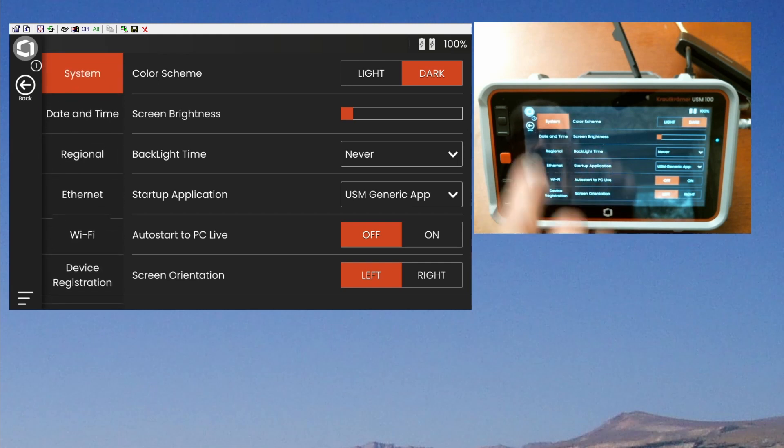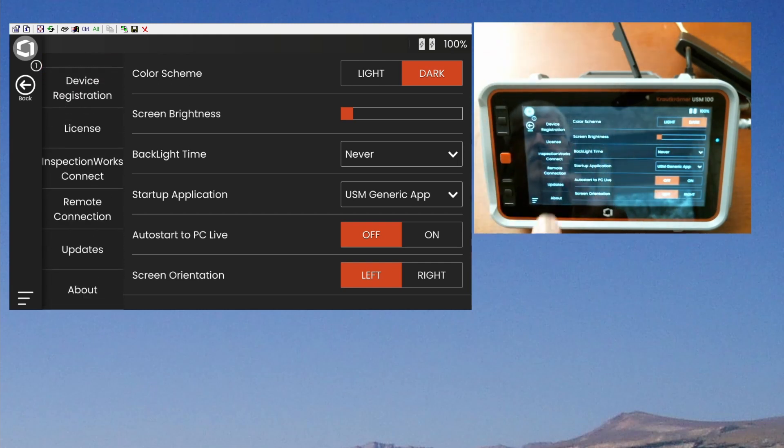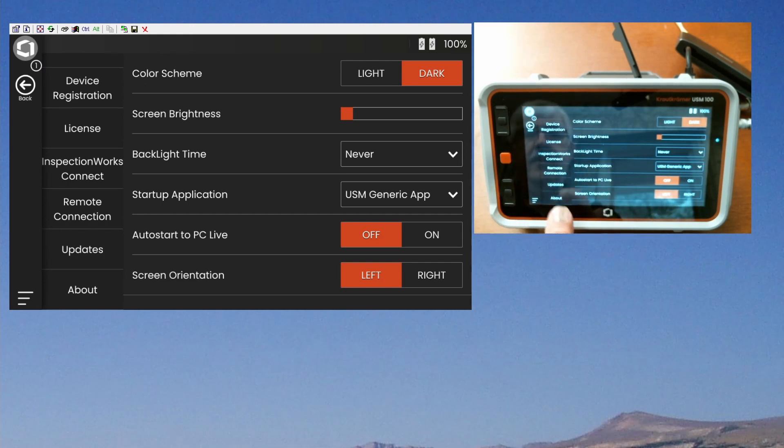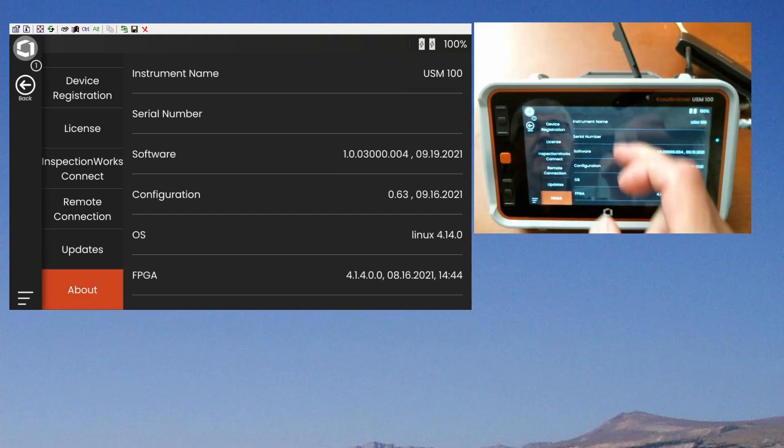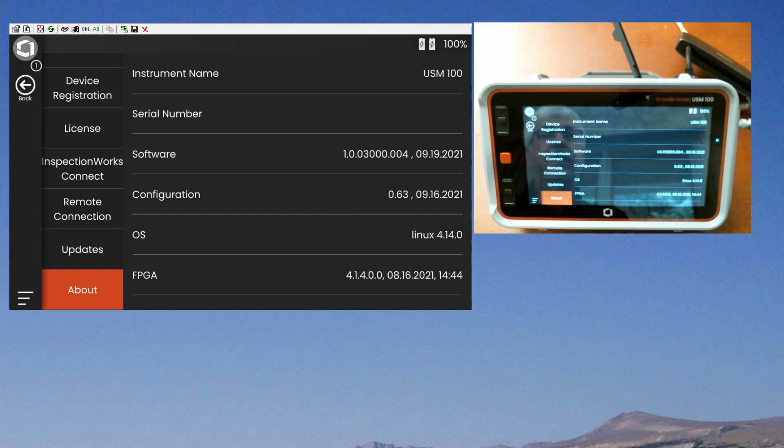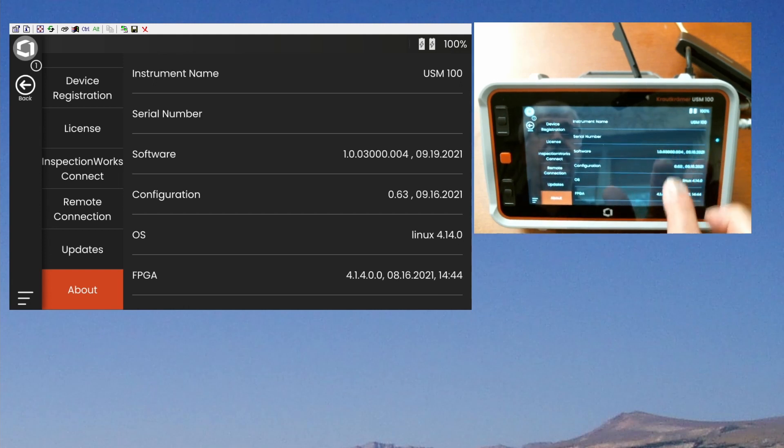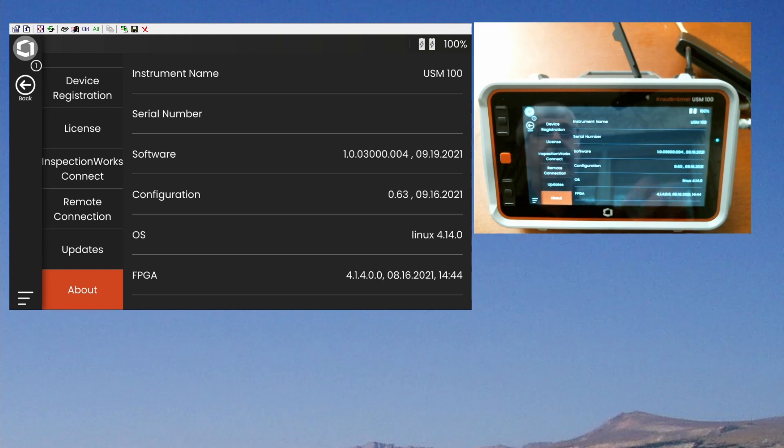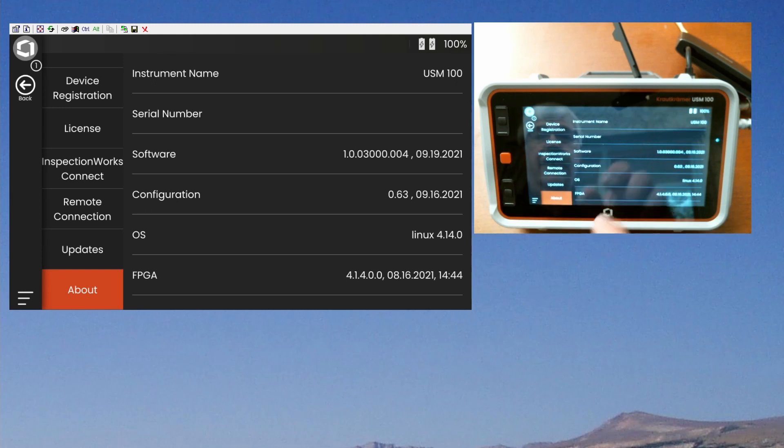You can swipe the list down and up. One of the first things you want to do is swipe it all the way up so you can see the About button on the bottom. If you touch About, this menu will list a number of important parameters about your instrument, including the version of software that's installed. We can see on my instrument, I have 1.0.03000.004, built on the 19th of September. That happens to be the first officially released version of code available for the instrument. So mine's up to date, but this is where you would come to find out what version of code is on yours.